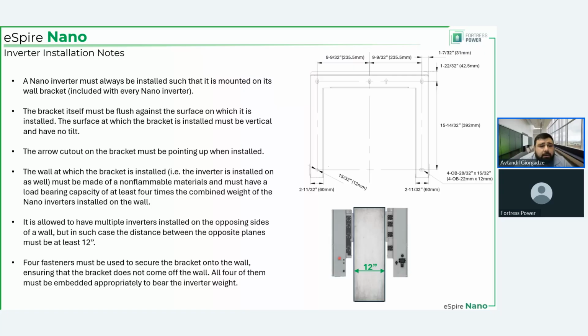The nano inverter must be installed such that it is mounted on the wall bracket. As I said, you mount it on the wall bracket, nothing else. The wall bracket itself you affix to the wall or some kind of other vertical surface, as you see on the slide. That surface, wall, or structure must be able to withstand 4 times the combined weight of the inverters on that structure. If it's one inverter, the total weight of one inverter multiplied by 4. If it's 4 inverters, the total weight of 4 inverters multiplied by 4. That's what it's supposed to withstand.